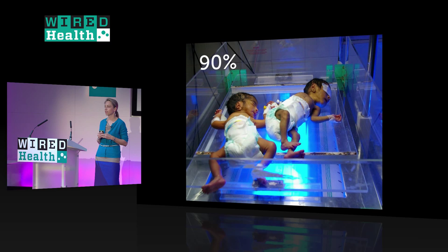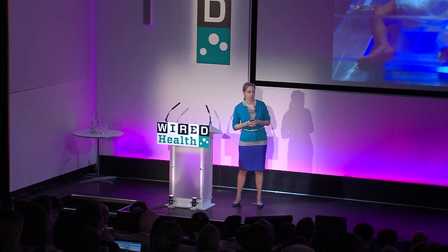One was phototherapy — blue light for severely jaundiced babies. The problem was described to us by an Indian doctor: mothers living in rural areas, particularly where a lot of moms are giving birth at home, don't have access to phototherapy. As we did some field work though, we saw something different. This is a picture from an urban hospital where very sick children are referred, and you can see it's not very effective phototherapy — two children in a bassinet, some of the bulbs burned out. We did research with Stanford University and found that ninety percent of phototherapy devices in four Indian states and one Nigerian state did not deliver effective phototherapy.